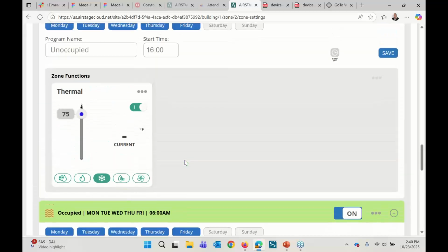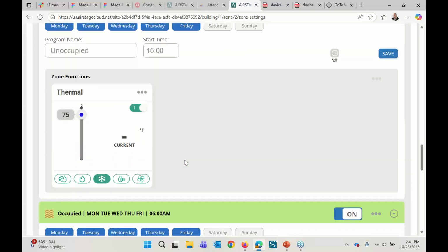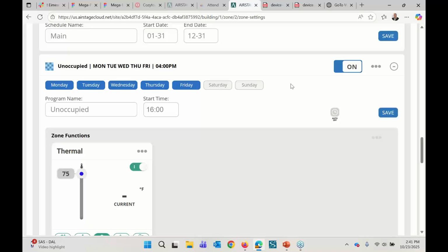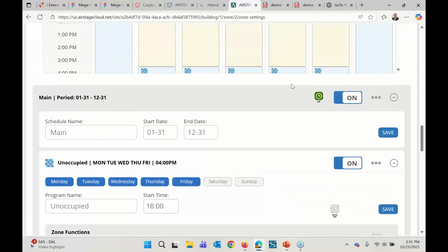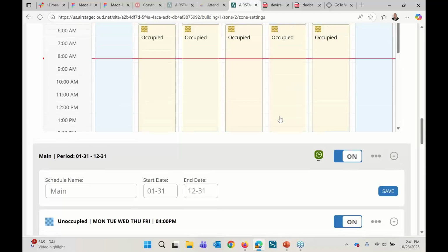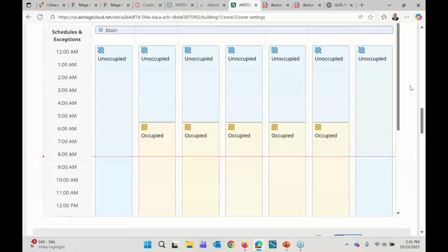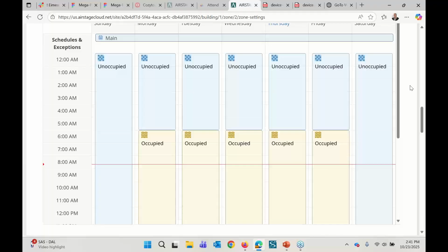Okay. You can make these schedules as simple or as complicated as you want them to be. We have some customers where their schedule is going to include VRF systems, rooftop systems, ERV systems. If you have an ERV on the site, you can add the ERV to any of these schedules. You can either run it concurrently with your VRF, or you can add it as a separate schedule item. So we have a number of customers that do that, and they use their ERV for pre-cooling before they want the VRF to turn on. And then the VRF runs, and then when the VRF becomes unoccupied, they turn the ERV back on again. So there's multiple different ways that you can configure these schedules.